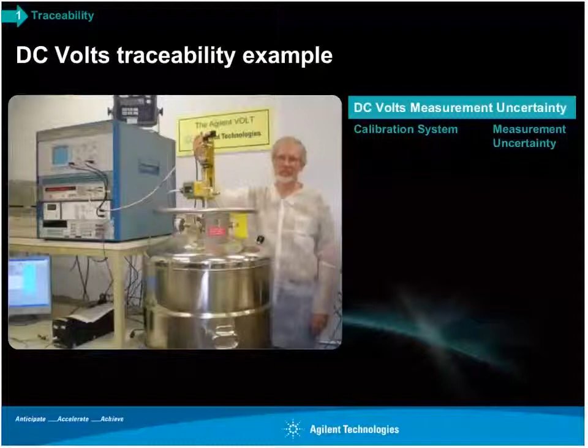Now I want to show you just briefly, we're looking at sort of a calibration tree, if you will, the primary standard being the very most accurate. So if you look at the measurement uncertainty for DC volts, you see that it's 2 parts in 10 to the -7th. So that's really as a worldwide standard. And by the way, if you're comparing one of these, how accurate is this compared to another one? That's not really a calibration. That is more where you send one around and say, this is what I got, what did you get? So there you can just compare them to make sure that nothing is off wildly, because they are the top of the traceability chain.